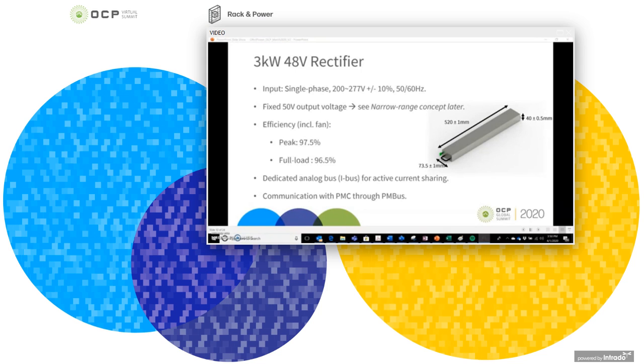At the output side, we plan to use active current sharing for the tightness of the spec. However, when you have transient dynamic loading, I believe this will go to voltage droop sharing mode. And obviously, it would be a lot better. The control loop needs to be worked on much harder if you want to have active current sharing only. Especially with 12 power supplies, it's going to be a little bit of a challenge. So we decided that we need to have both implemented.